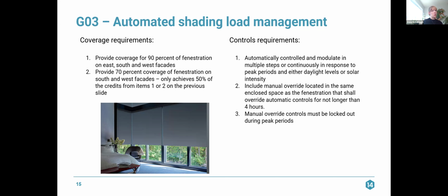There are also controls requirements for the shading devices. They have to be automatically controlled and modulate in multiple steps or continuously. Like dynamic glazing, if you've seen it, operates continuously. It doesn't necessarily have to have steps. They must respond to peak periods and to either daylight levels or solar intensity. So if we do have dynamic glazing, we also have to be able to modulate it based on the peak period.